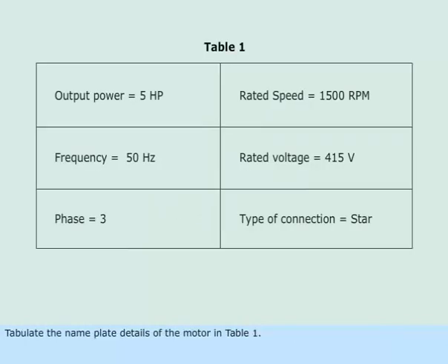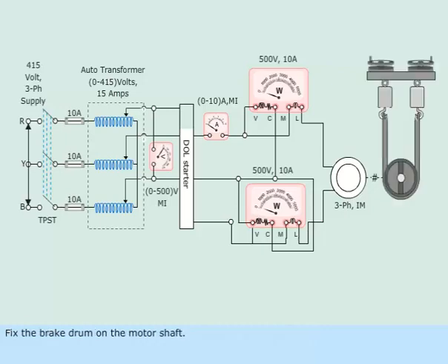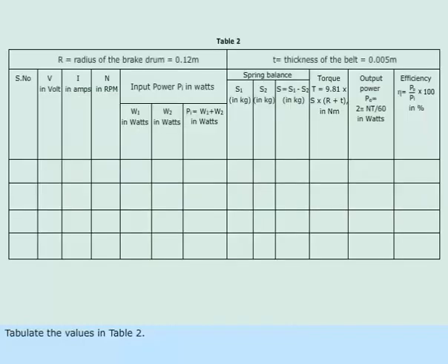Tabulate the nameplate details of the motor in Table 1. Make the connections to the motor as per the circuit shown above. Fix the brake drum on the motor shaft. Measure the radius of the brake drum and the thickness of the belt. Tabulate the values in Table 2.